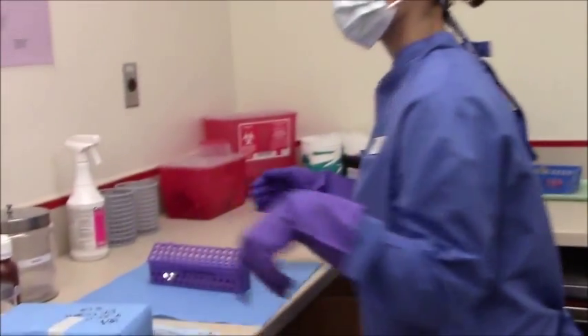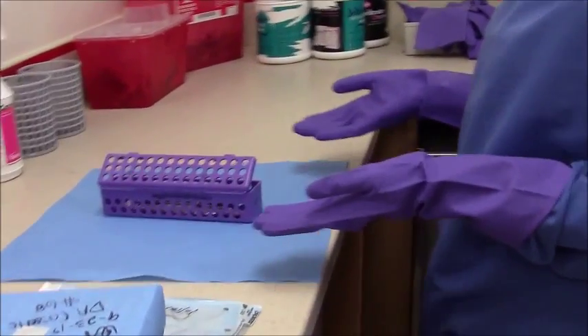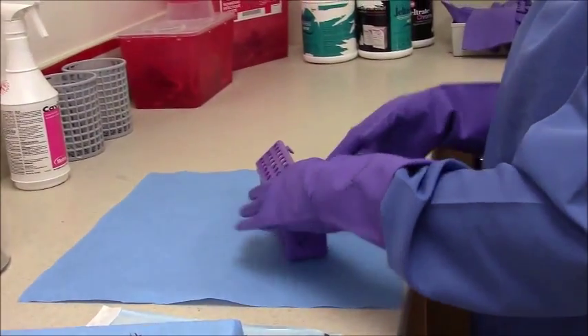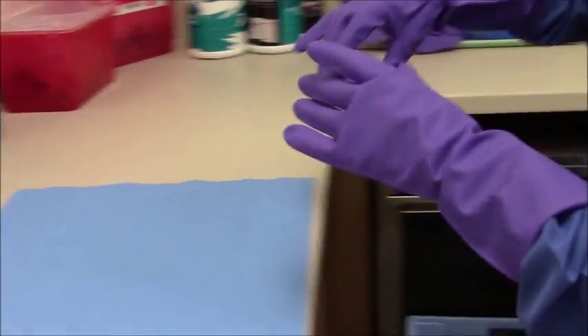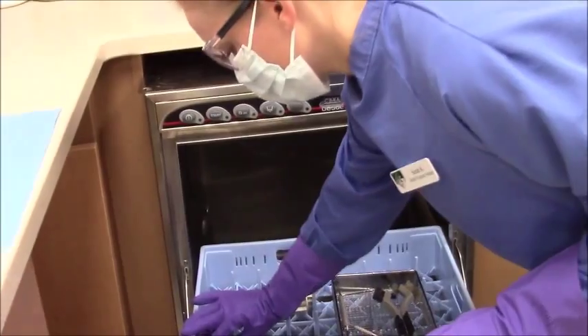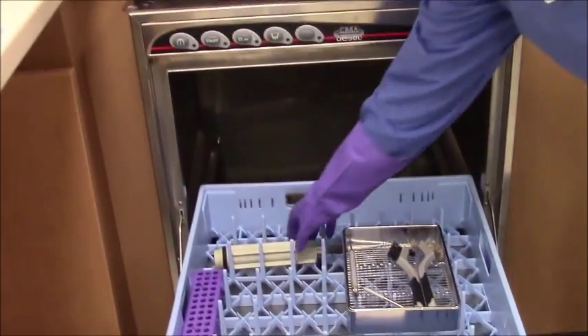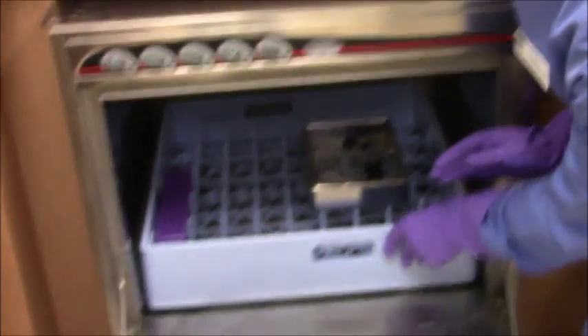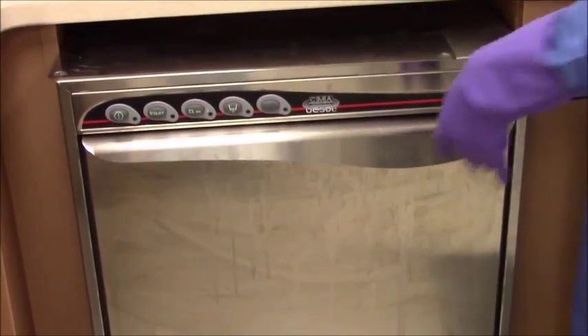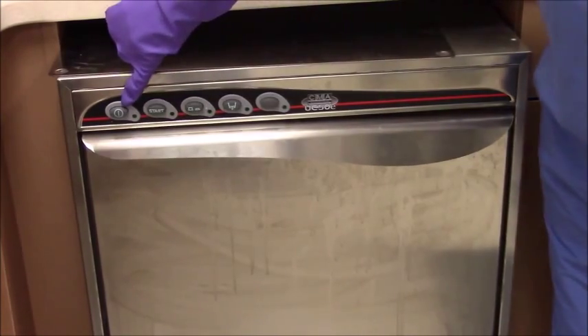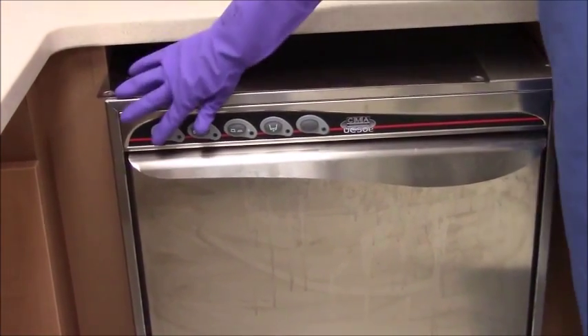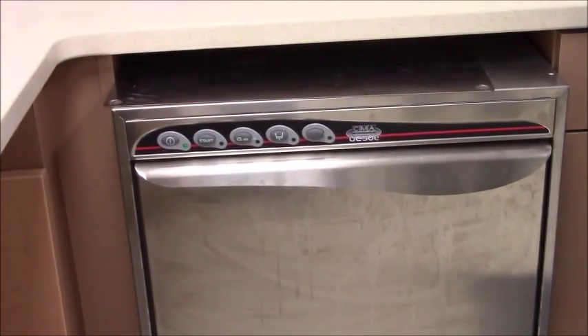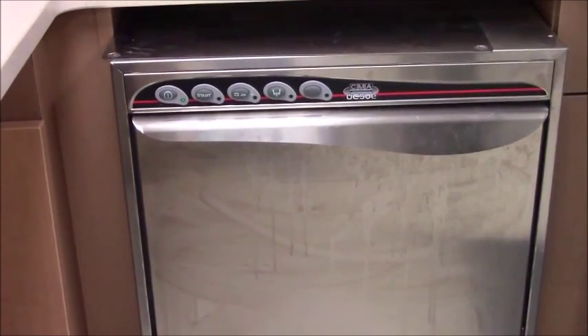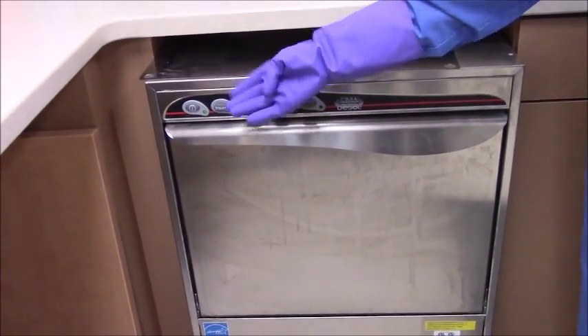Once in the sterilization room, unwrap the sterilization wrap, then take instruments to the CMA dishwasher to pre-clean. Before pre-washing, insert the overflow tube inside the wash tank. Close the washer door. Turn the wash on by pressing the power button. Wait for water to fill up. When the water level is reached, press start to pre-clean instruments.